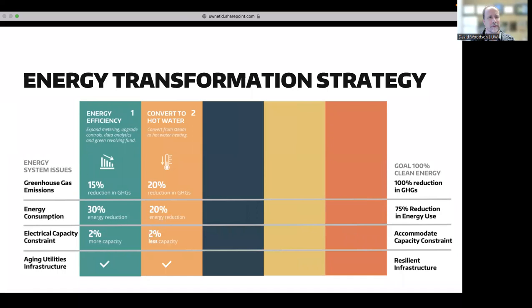This is really the linchpin. I was describing reclaiming waste heat from the cooling towers, but we can't do that with the steam system because it's too hot. We need a distribution mechanism where the temperature is lower. This is the big project we did at UBC, converting the campus steam distribution system to hot water. Everything else I'm going to talk about is dependent upon this happening.